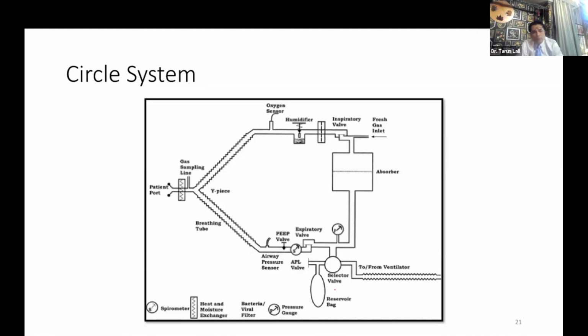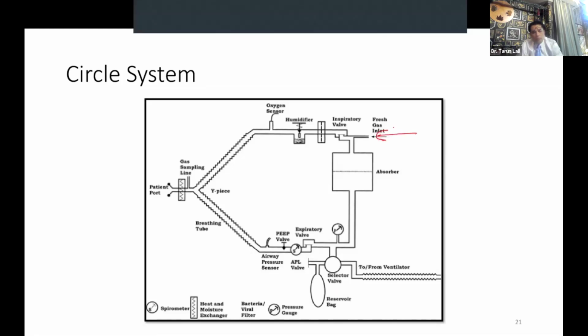So the design of the circle system is simple. We have the fresh gas inlet. As the gases come in, the first thing that we encounter is the inspiratory unidirectional valve. Beyond that, we have the humidifier, the oxygen sensor, the gas sampling line, and finally the patient Y-piece. Then we have the expiratory limb. In the expiratory limb, again, we have the pressure sensor and the PEEP valve. The PEEP valve can have three different locations, and we will come to it just now.